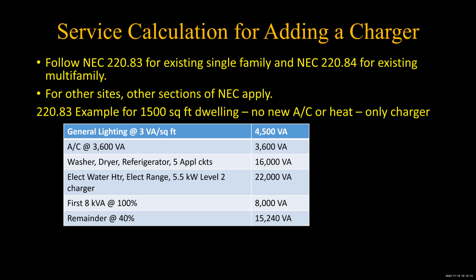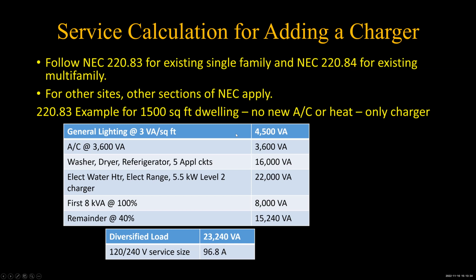So the rules: you take the first 8,000 volt amps at 100%, that's 8,000, instead of the first 10,000, because you've already included your air conditioning and so forth. The remainder comes in at 40%, or 15,240. So what does that mean? It means that you need a 96.8 amp electrical service to handle all that. The National Electrical Code says minimum electrical service has to be 100 amps. So that means you can add a level 2 charger at 5.5 kW to almost anything. But you should always do the load calculation first to make sure you're okay. You may have to upgrade the service. If so, maybe so. But remember, it's really only adding in 40% because of the diversification factor.